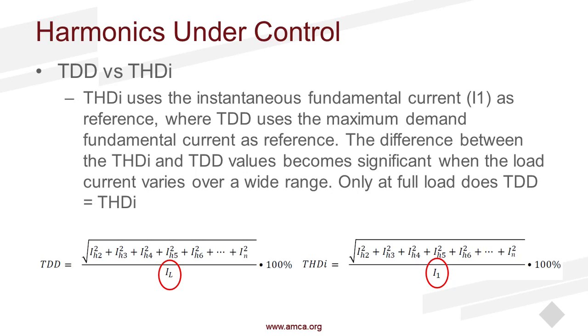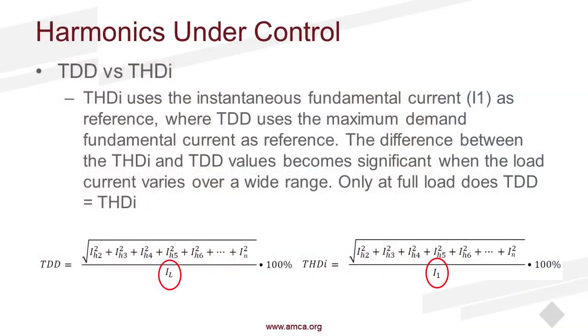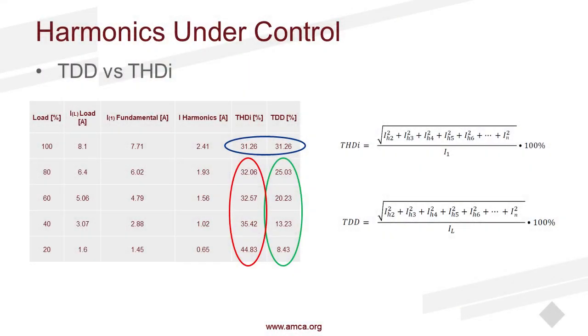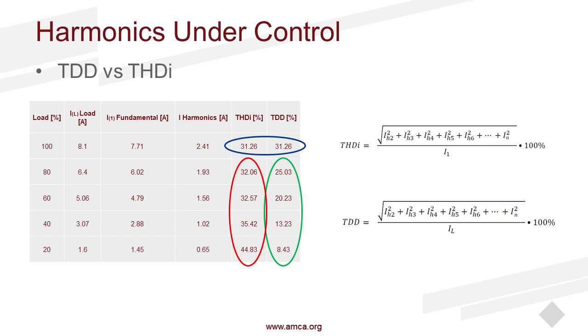So we can compare TDD, total demand distortion, with our total harmonic distortion current. In a full load situation, these would be the same. But when you start looking at partial loads, this is when they start to differ, because we're looking at the ratio of the fundamental current versus the ratio at the full load current. And we can look at an example. So here we're looking at our THDI, TDD, and then you have your current load, your fundamental current, and then your harmonics current. At full load, we can see that your THDI and your TDD are the same. As you go to a partial load, though, you are now seeing that the total harmonic distortion current is increasing in percentage, but your total demand distortion is decreasing.